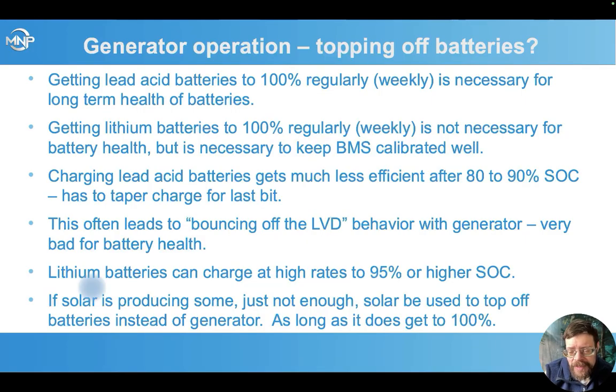What this often led to is behavior with generator charging where we'd wait till the batteries were dead, charge them up halfway or most of the way until the lights stayed on, but then not all the way. And this led to very poor battery health and sulfated lead acid batteries, because they never got completely full, just because it was so obnoxious to get them completely full with the generator. Lithium batteries, they can be charged at high rates to 95% or even higher before you have to start tapering.